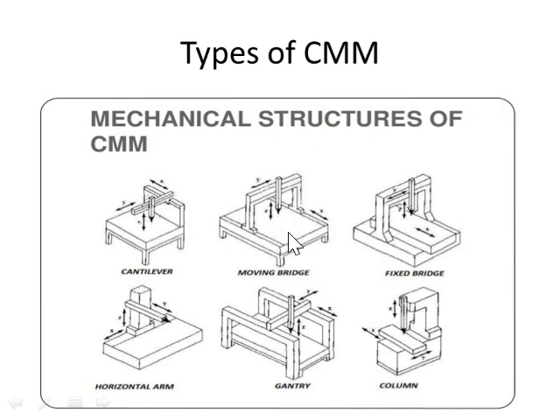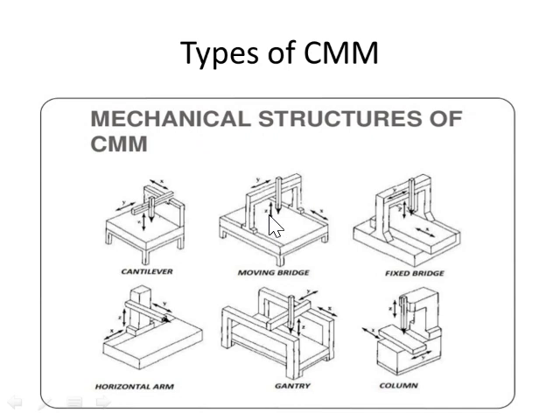The second type is called moving bridge. In cantilever, one end is fixed and another is free. In the bridge type, both ends are fixed. This is the CMM unit and this touching point is called the probe. The bridge moves forward and back in the horizontal direction, and the probe moves in the vertical direction and across the flat surface. That's why we call this the moving bridge type.